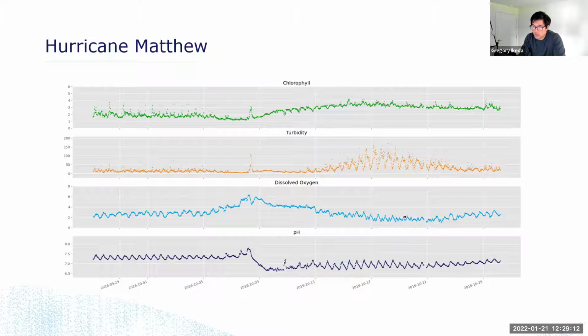So it's possible that we had some sediment caught in our dissolved oxygen sensor, some sediment caught in the plumbing that could be affecting our measurements. And being able to see this turbidity really tells us, okay, this is a good point to go and maintain our instruments, because we know that this signal could be detrimental to our data quality. So that's a really important aspect of having multiple data points, is that not only do you get a more comprehensive scientific picture of what's going on in your environment, you also get some maintenance and quality metrics on your instrument itself, so you can make some decisions on when you need to go out there and service it.